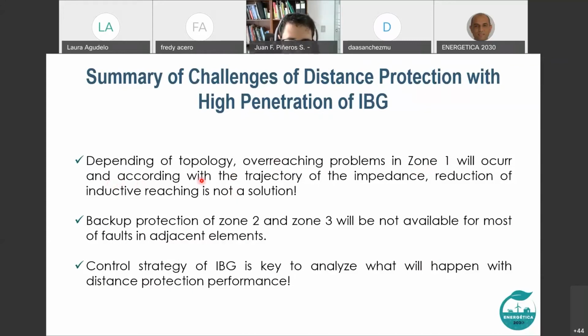An important reduction of the inductive reaching, which is normally the solution for these problems, is not working because, as I told you, the problem is coming from the right. As well, backup protection in zone 2 and zone 3 will not be available for most faults in adjacent elements.